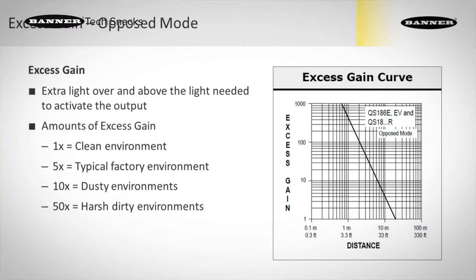To show the amount of excess gain a sensor has, we have an excess gain chart. This is a logarithmic, or log-log for short, chart that shows you the excess gain. I can look at this chart and see that at one — which is the amount of light a sensor needs to turn on — an excess gain of one will turn on a sensor's output.